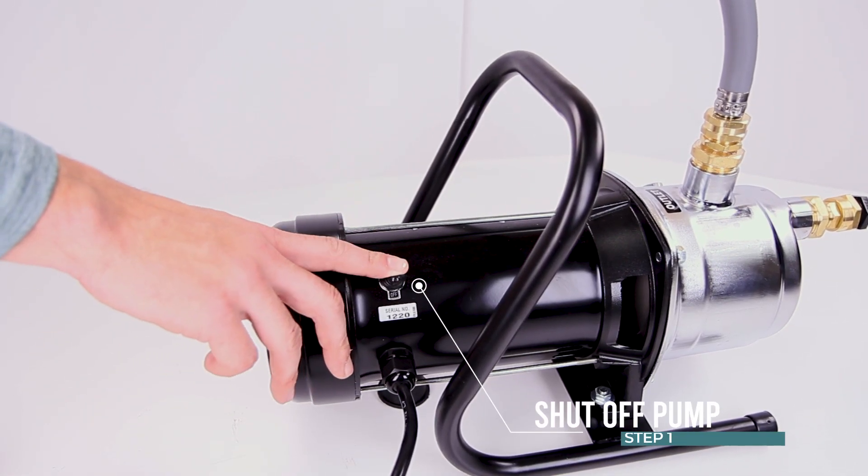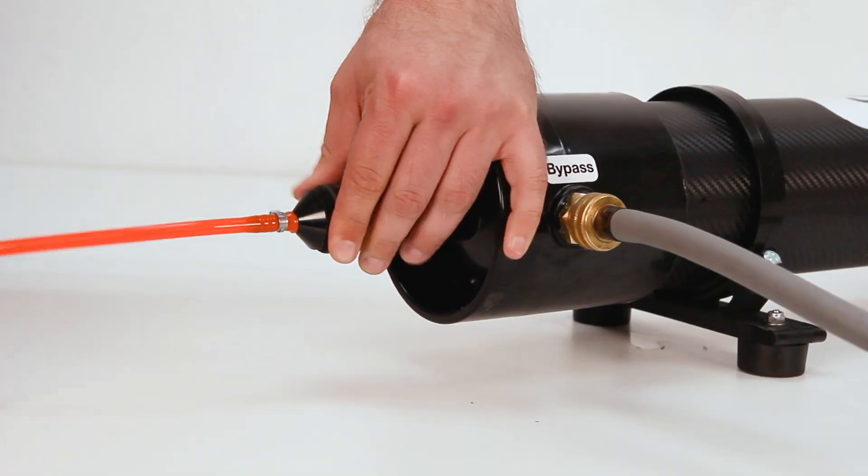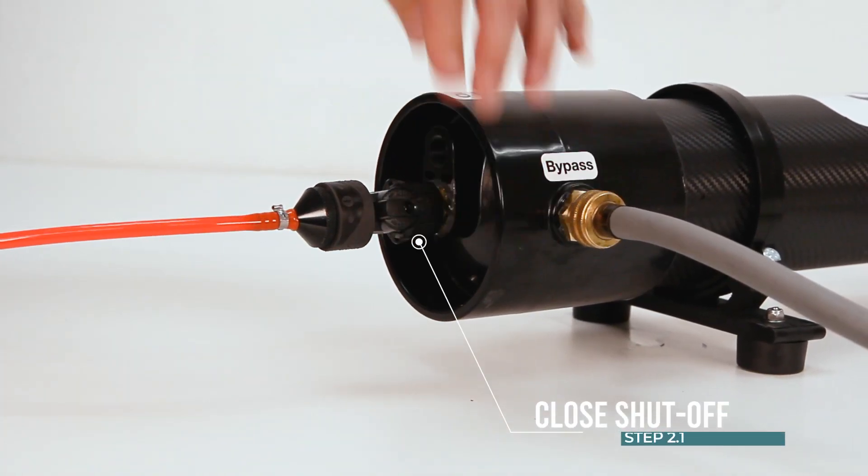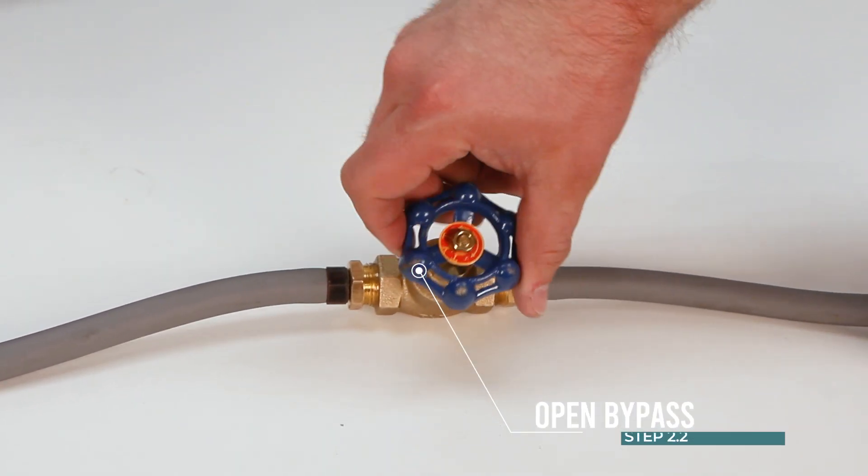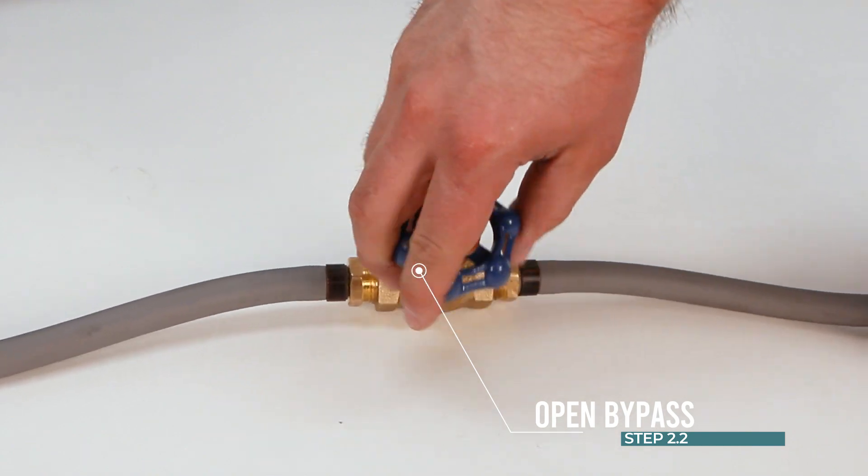Shutdown procedure: If using a pump, shut off the pump before turning off supply water. Close the shut off valve to the pole. Open bypass valve to fully open position and flush out the system for three to five minutes. Turn supply water off and disconnect the water line.